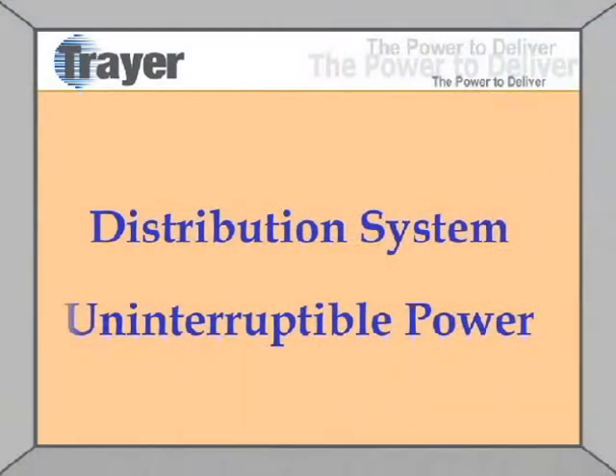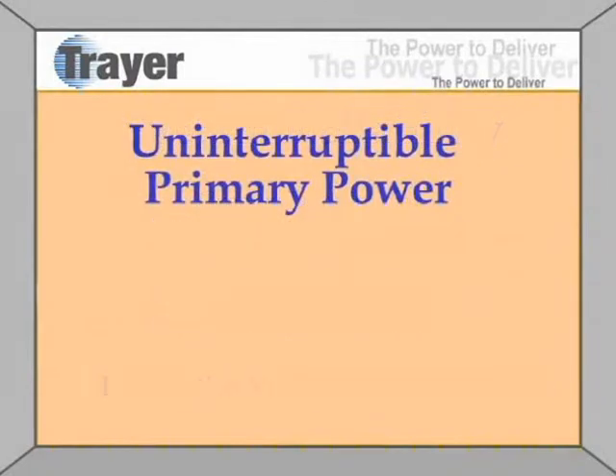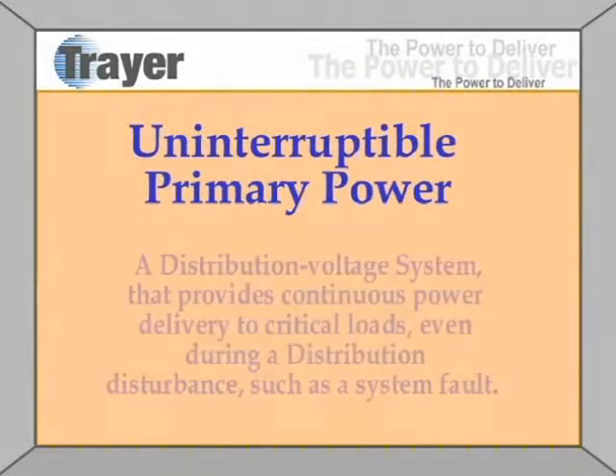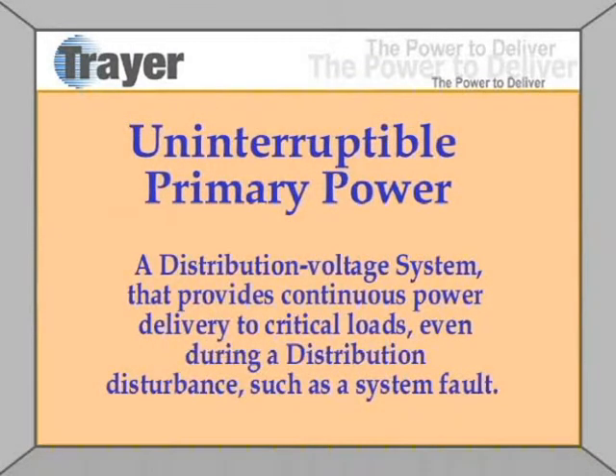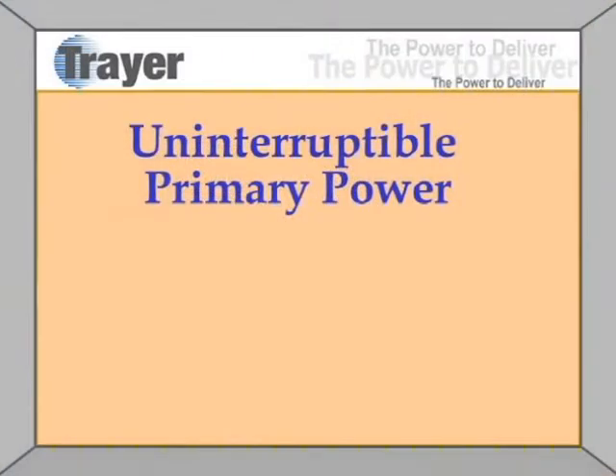Topic today is distribution system, uninterruptible primary power. You would have a distribution voltage system that would provide continuous power delivery to critical loads, including during a system fault. I'm talking about a loop system where you have a cable fault on it, and we still continue to serve power to all of our customers. A zero-cycle interruption: uninterruptible primary power.